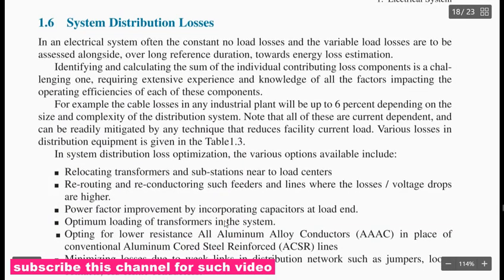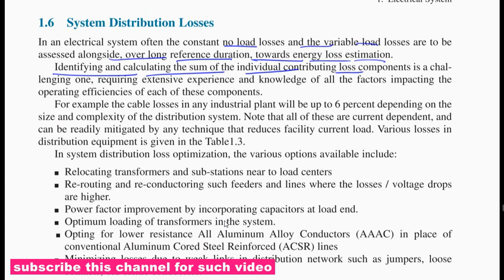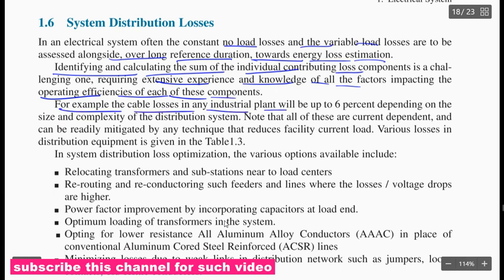System distribution losses. In the electrical system, often the constant no load losses and variable losses are to be assessed over a long reference duration towards the energy loss estimation. Calculating the sum of individual contributing loss components requires extensive experience and knowledge of all the factors impacting the operating efficiency of each of these components. For example, the cable losses in any industrial plant will be about 6%, depending on the size and complexity of the distribution system. All these are current dependent and can be minimized by any technique that reduces the power current, such as improving the power factor, and so on.